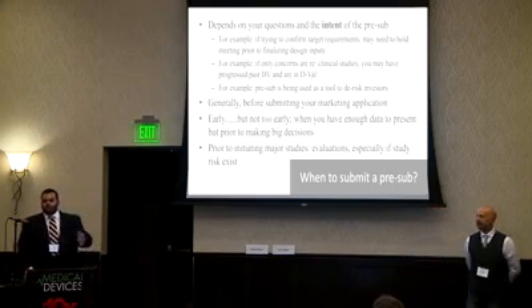So again, there's no right answer to that. It's, do you think that supplier represented such a risk to your product regulatory strategy that it needs to be addressed? That probably wouldn't qualify for a pre-sub alone, right? Because that's maybe considered a design change, a manufacturing change that you would have to assess internally. FDA has guidances on assessing those types of changes. But again, if it's a class 3 device and it's a pacemaker battery supplier and there's a lot of implications for that, that might be sufficient information to go to the agency for.